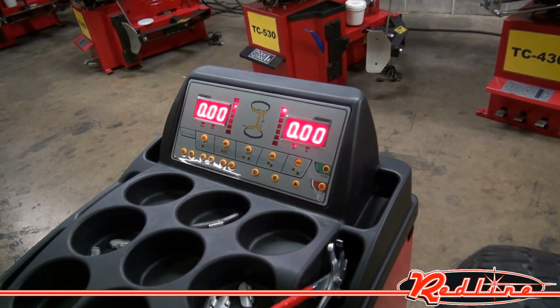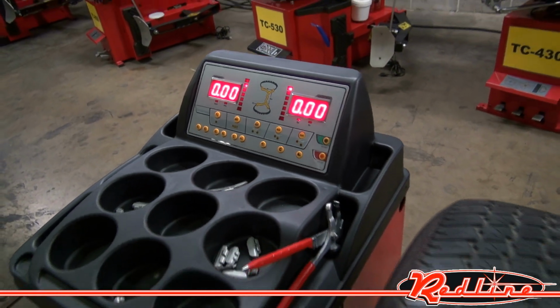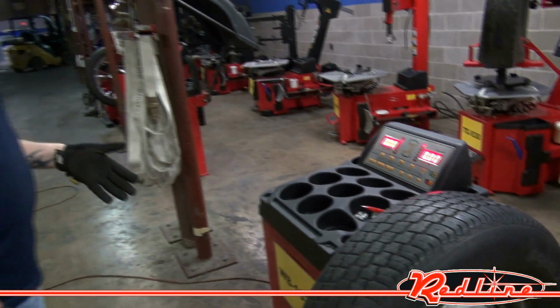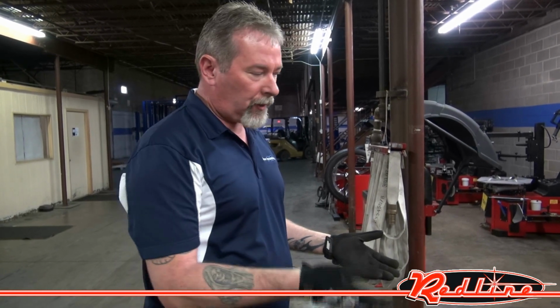We do recommend performing this calibration procedure, I would estimate every 6 months or so. If you see that the machine is giving false readings, or chasing weights is what we call it, go ahead and calibrate the machine again and proceed with balancing.